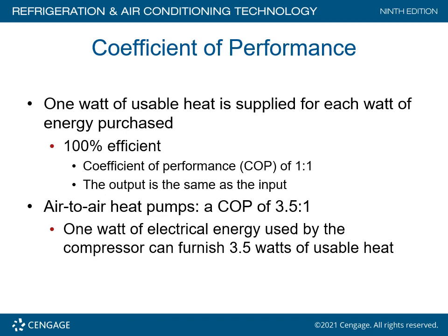Coefficient of performance, COP. One watt of usable heat is supplied for each watt of energy purchased. 100% efficient is a coefficient of performance, a COP, of 1 to 1. The output is the same as the input. Air-to-air heat pumps have a COP of 3.5 to 1, which is good. One watt of electrical energy utilized in the compressor can furnish 3.5 watts of usable heat. That's not a bad combination. You'll see what happens if you use strip heat.